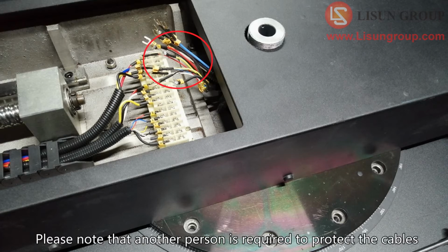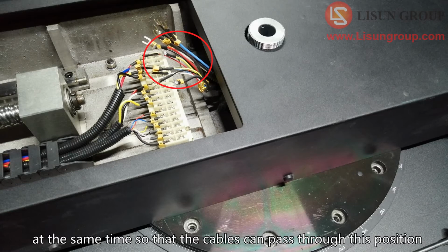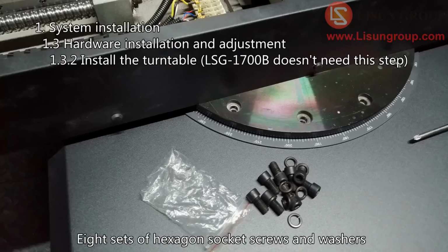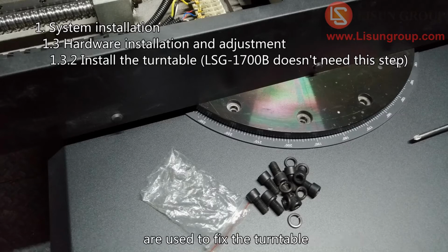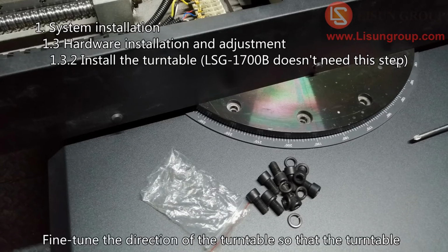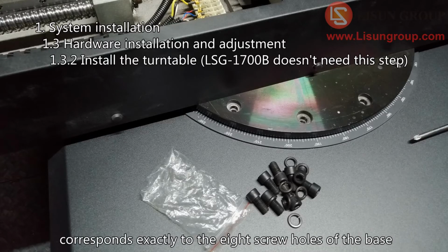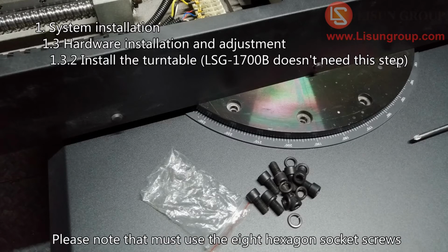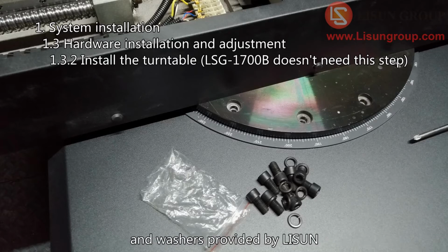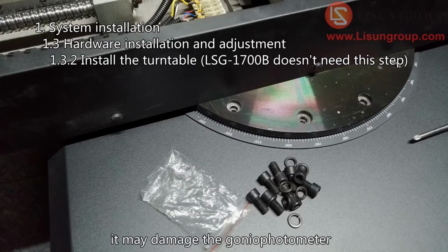Please note that another person is required to protect the cables at the same time so that the cables can pass through this position. 8 sets of hexagon socket screws and washers are used to fix the turntable. Fine-tune the direction of the turntable so that the turntable corresponds exactly to the 8 screw holes of the base. Please note that you must use the 8 hexagon socket screws and washers provided by Lisun. If you use different screws or washers, it may damage the goniophotometer.